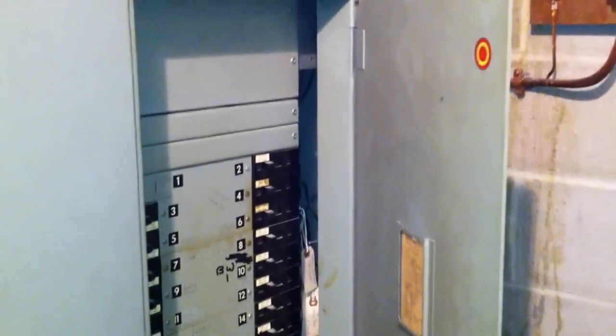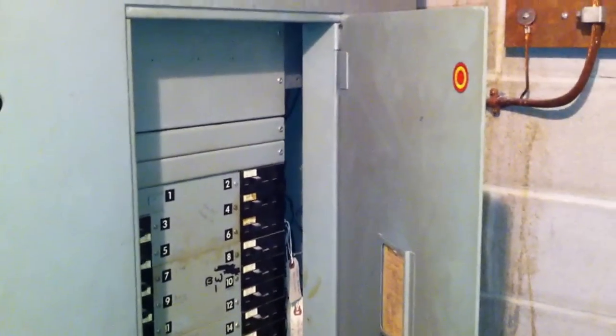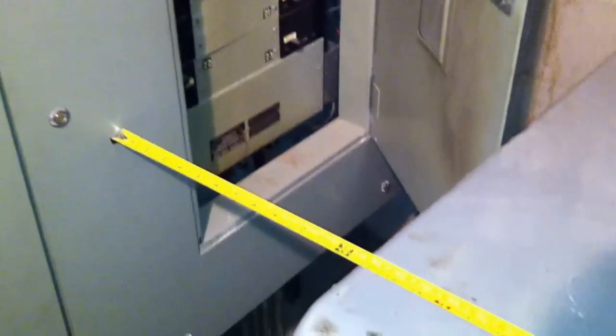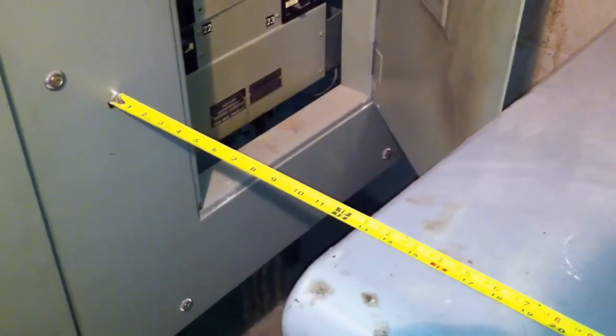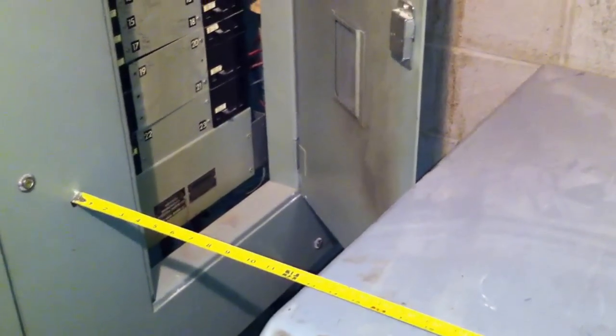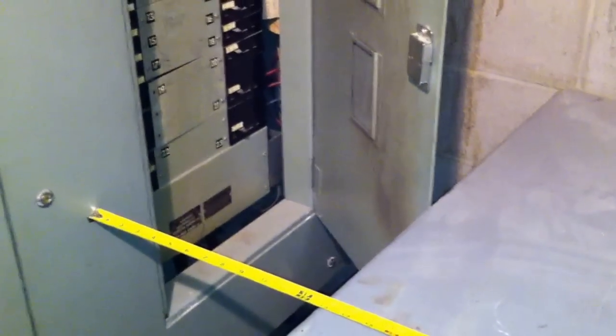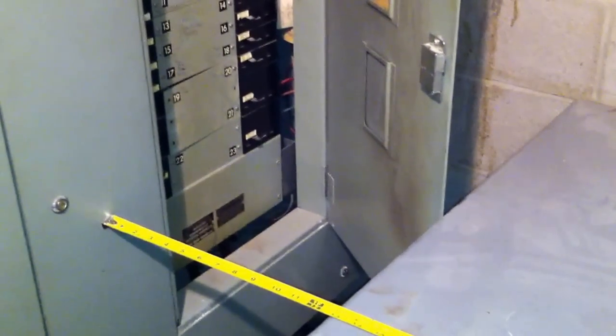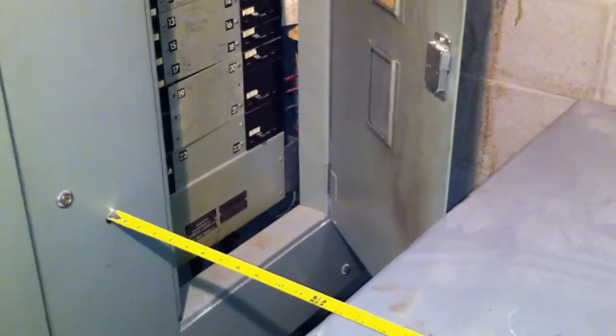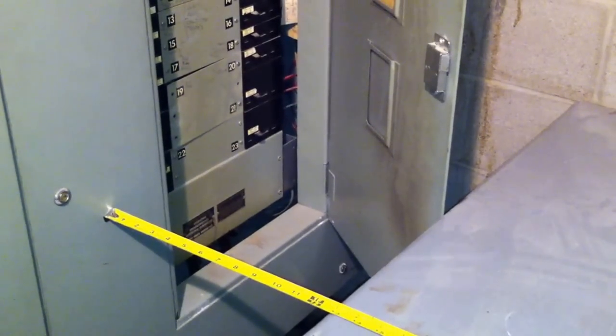does not open quite to the required 90 degrees. So these are all violations of the workspace requirements in Section 110.26(a). It would be very dangerous to work on this panel board — you'd have to either cram yourself in there or stand way back and try to work on it safely. In any case, we've got a few violations of workspace requirements. This is Russell Blank, NEC consultant for EC&M magazine.